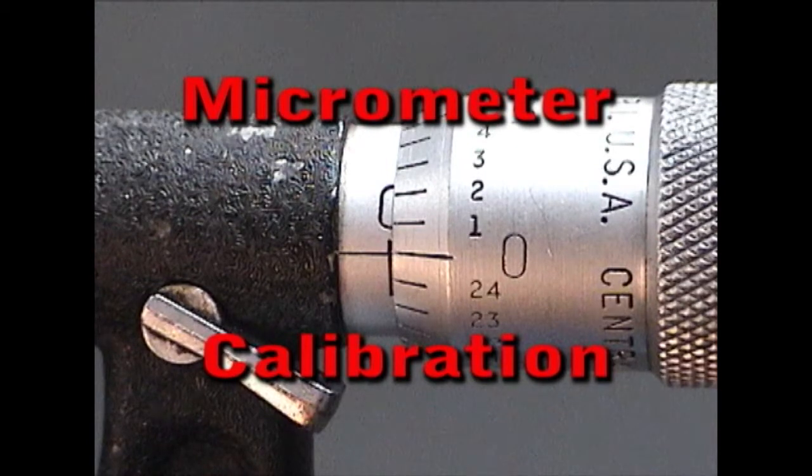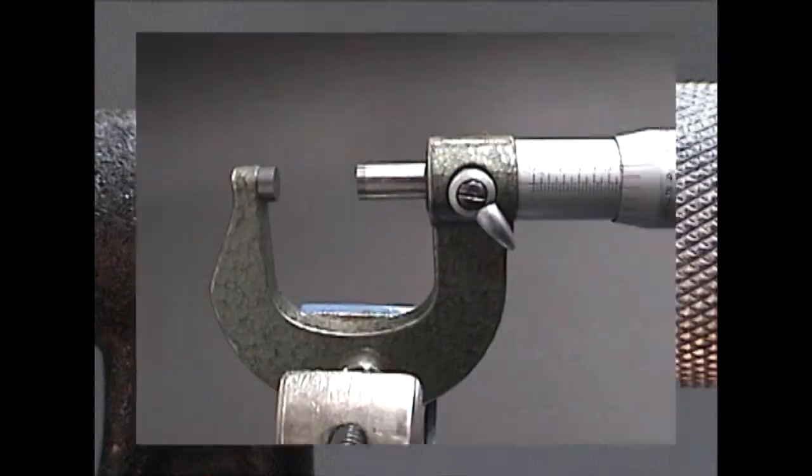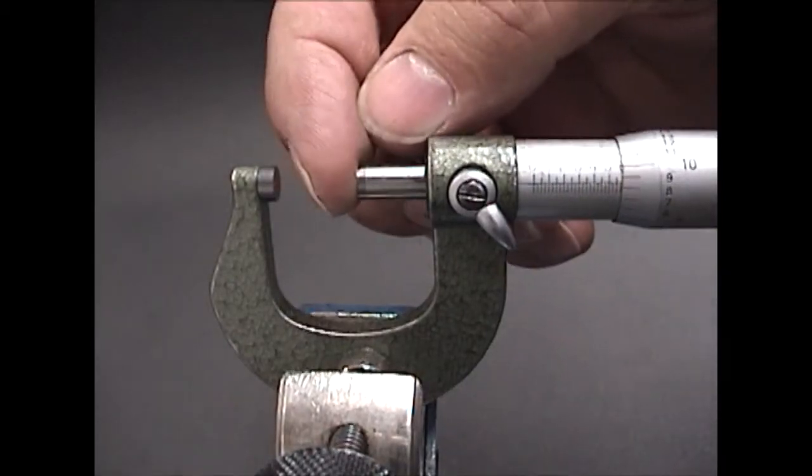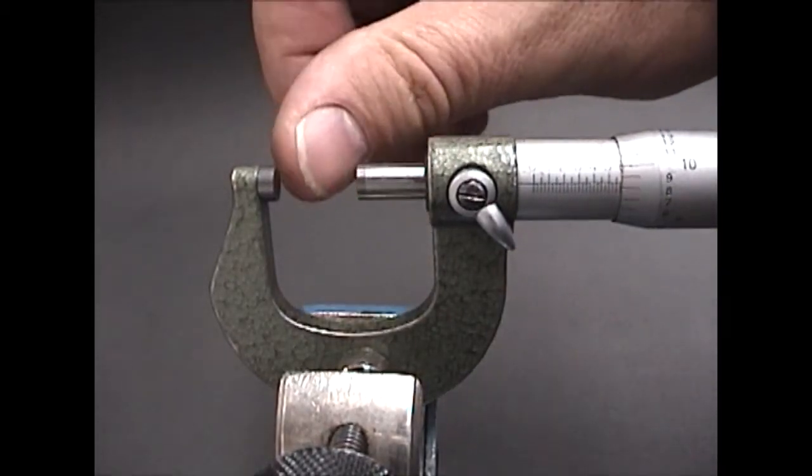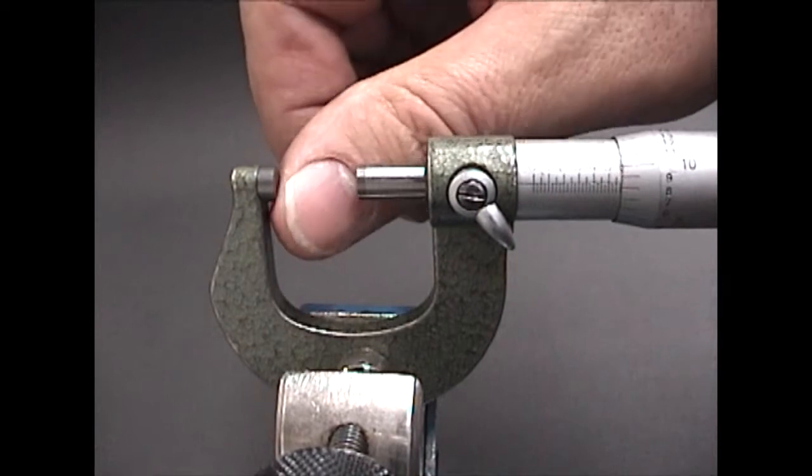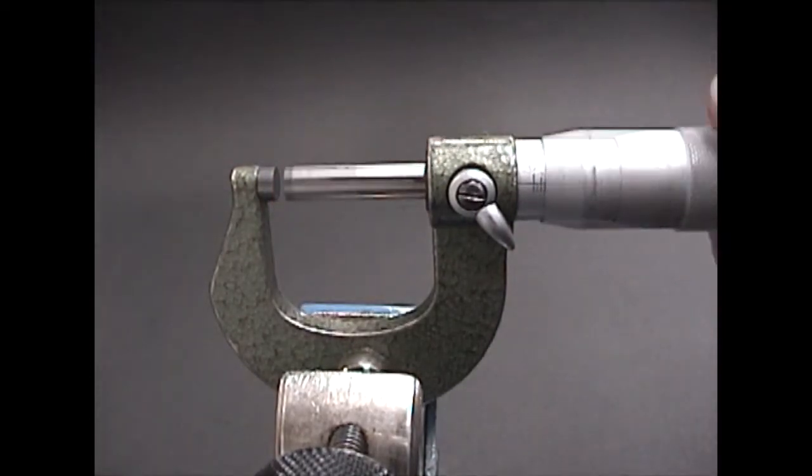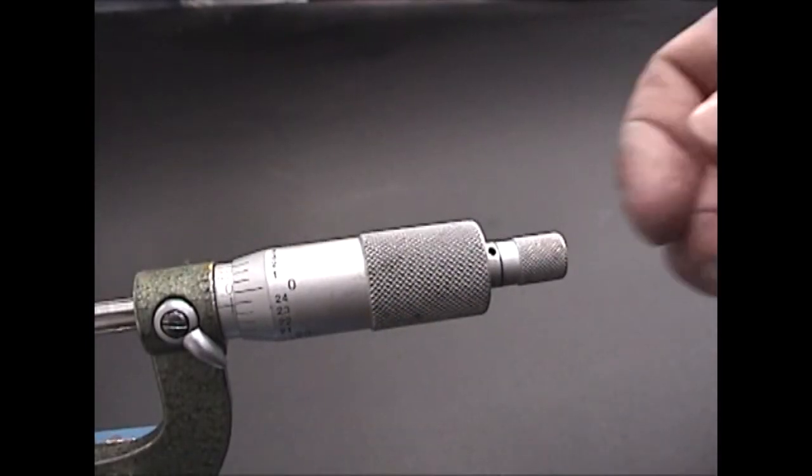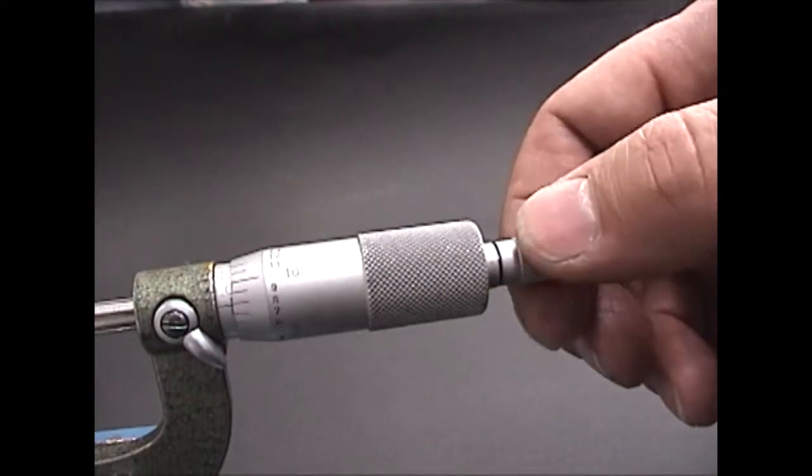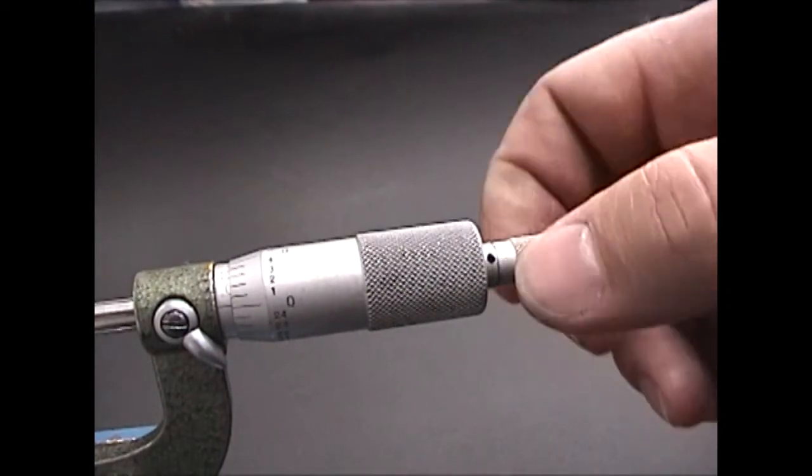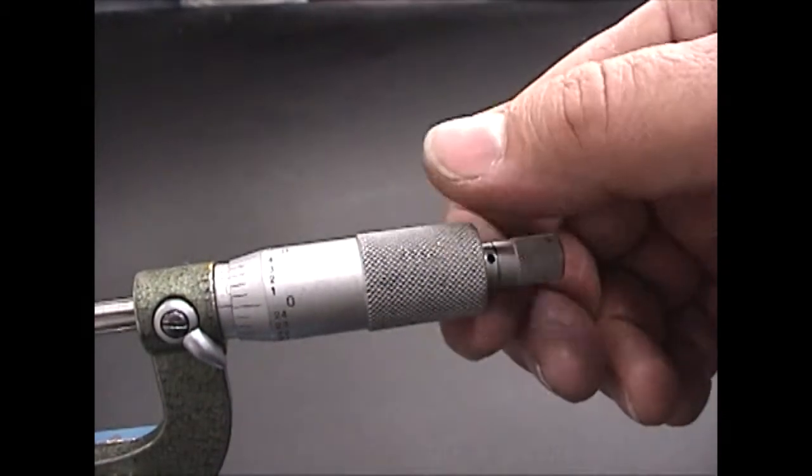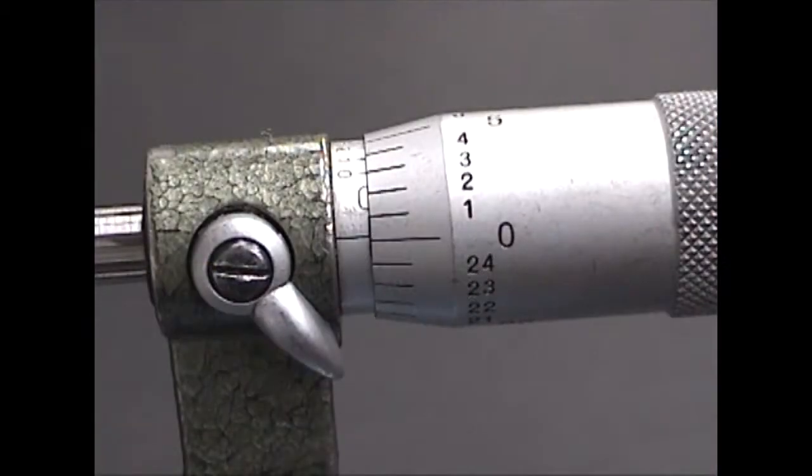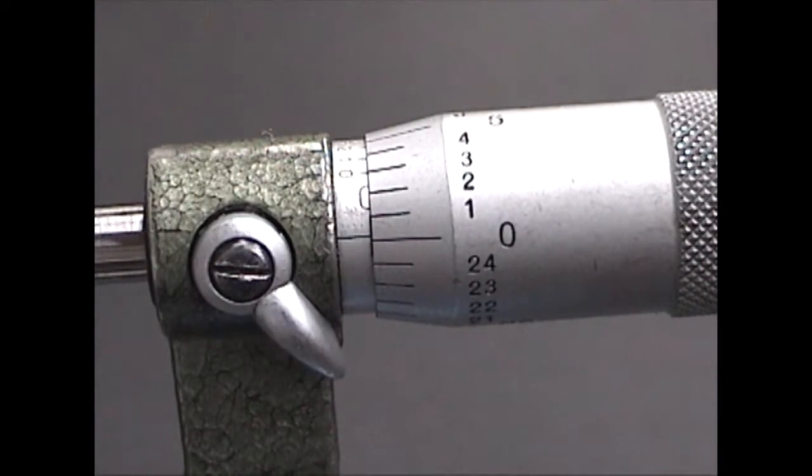Micrometer Calibration. Wipe all dirt from the measuring surface. Use a gentle spinning touch or use the thimble ratchet to close the micrometer. Check to see if the micrometer is zeroed properly.